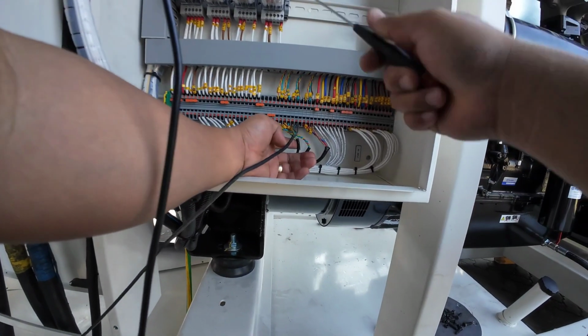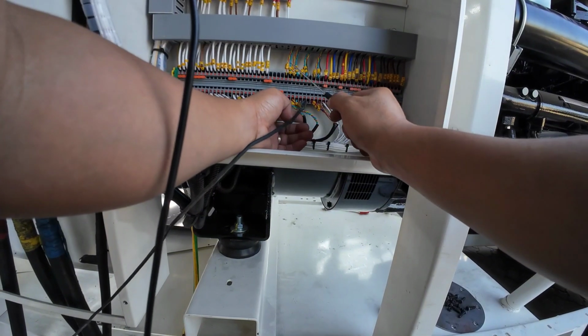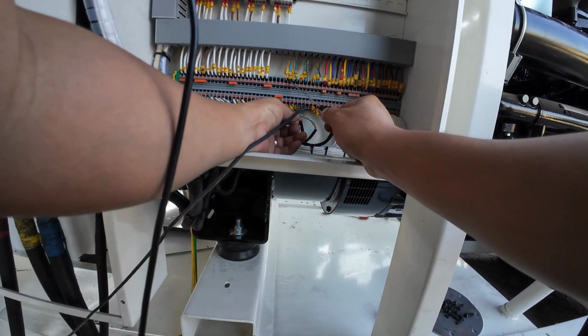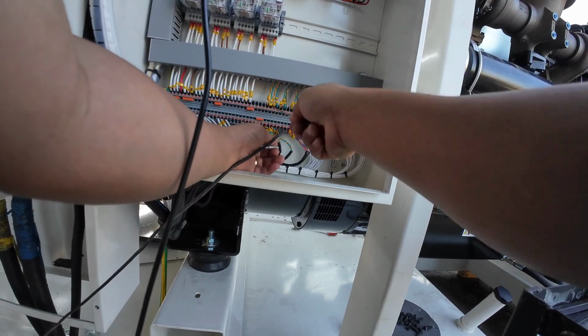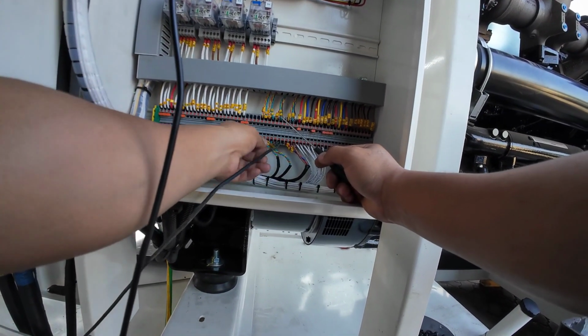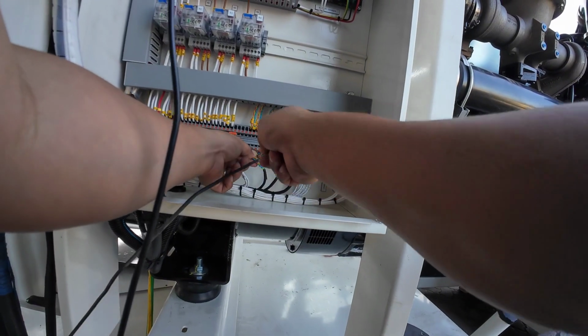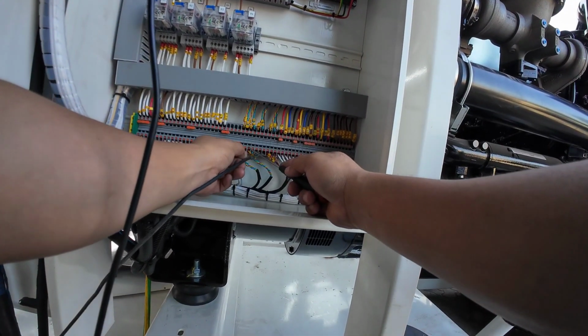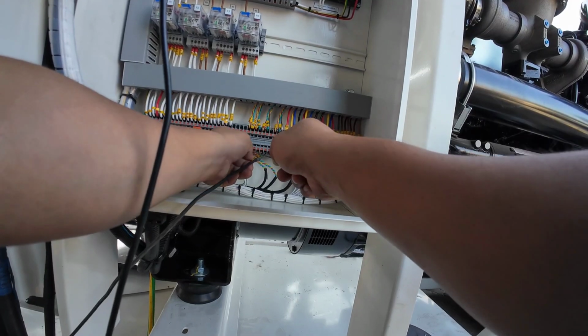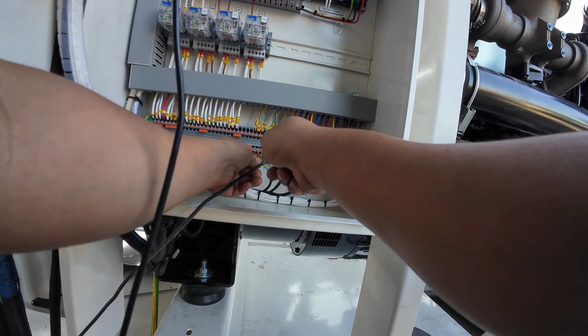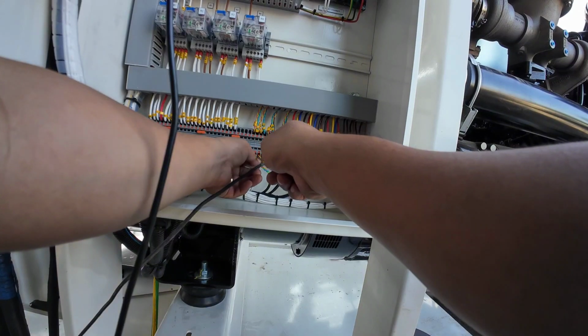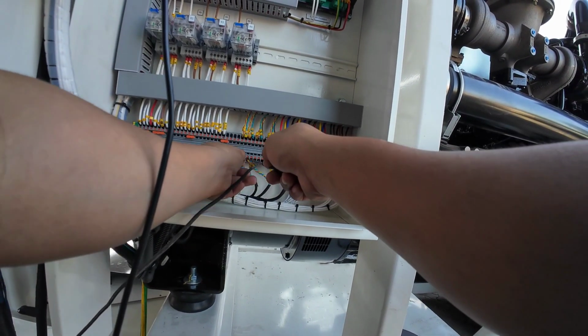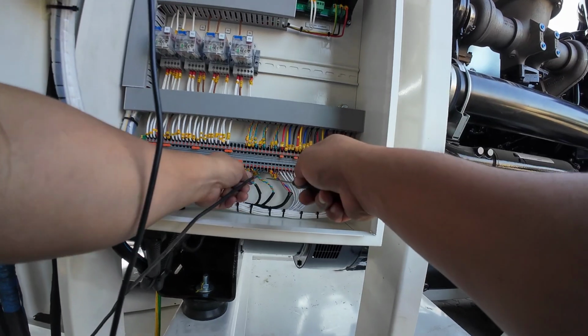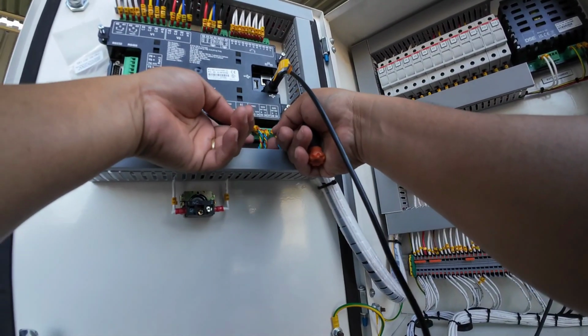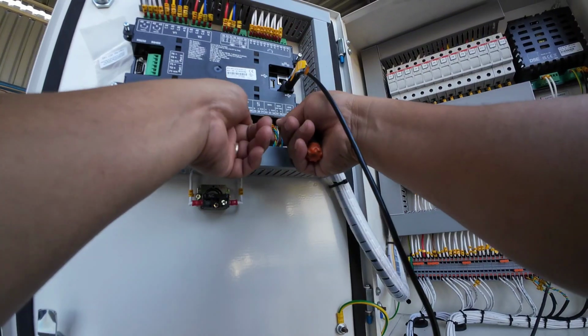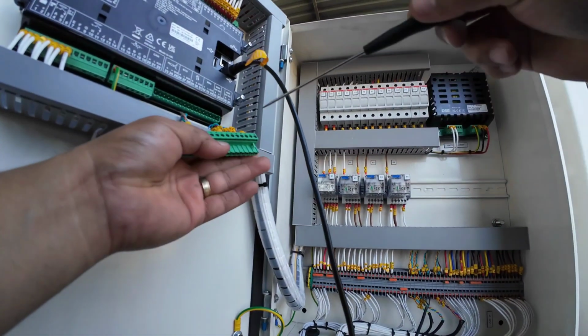In here I noticed there is no control for our speed, so I'm going to troubleshoot and check the connections to find out why we don't have control for our speed. I am removing the wiring to check for any loose connections and if it's correctly connected, and checking over to our terminal block and module connections so we can see clearly that we are in the correct connections.